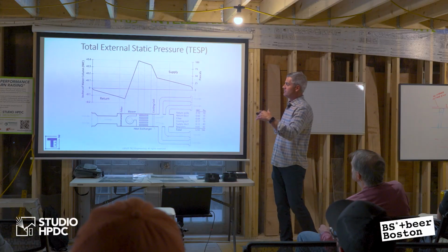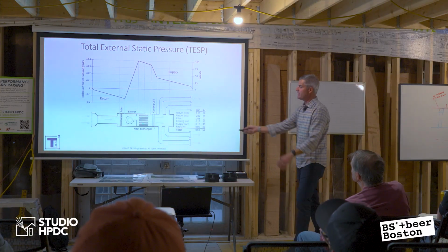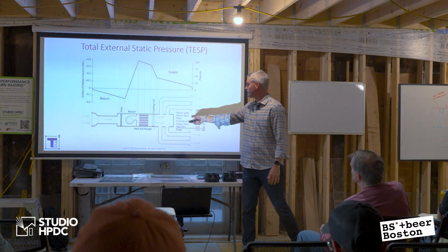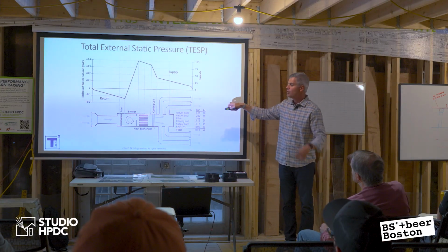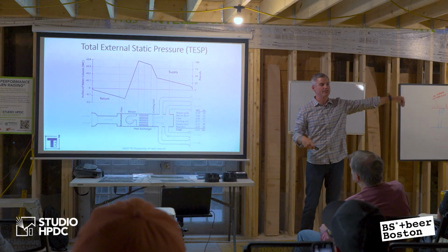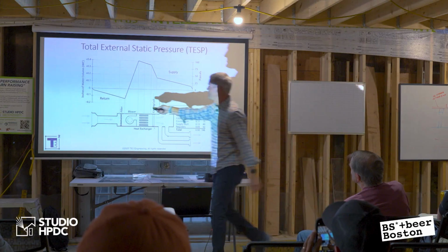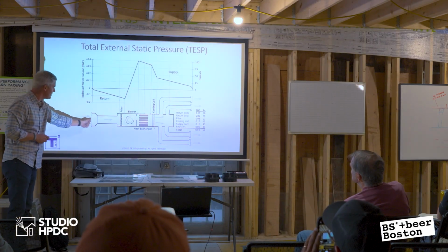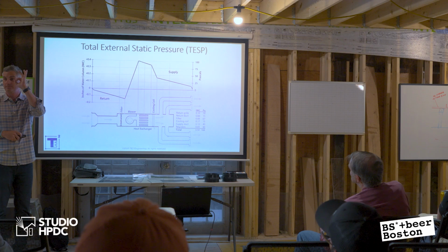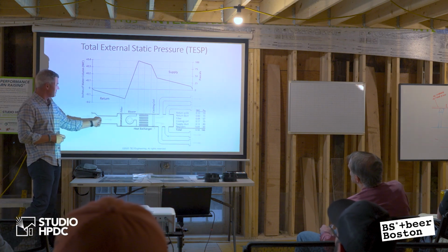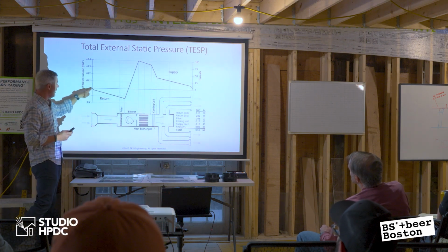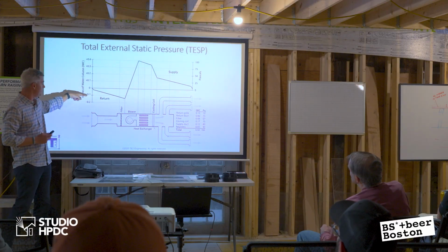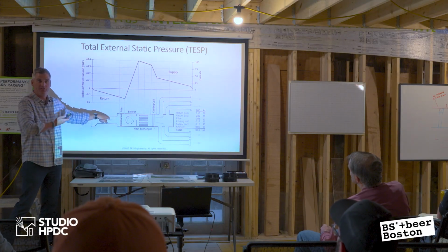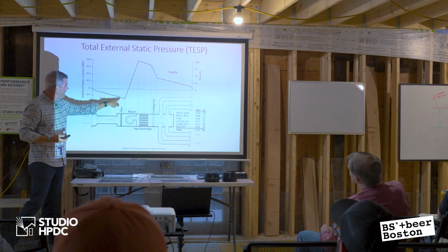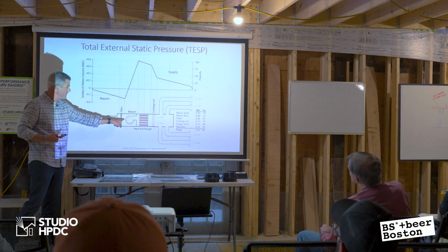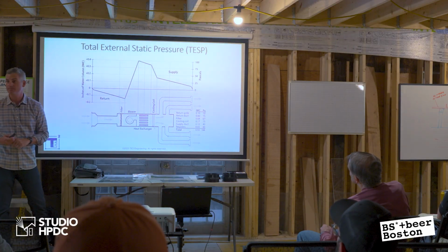So hopefully this isn't too technical, but if you look at an air handler, here's a return duct, here's a supply duct, and you were to map the pressure through that entire duct system, look at how it starts. It starts off at 0. So at the return register, if I measure the pressure, it'd be 0. If I measure pressure along the way with my manometer, my return gets more and more negative. It's on the suction side of the fan, right? So this is negative, negative, negative. Then I get to the return of the blower, and that's the most negative it will be.